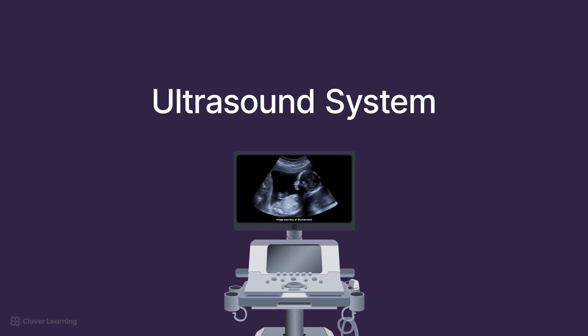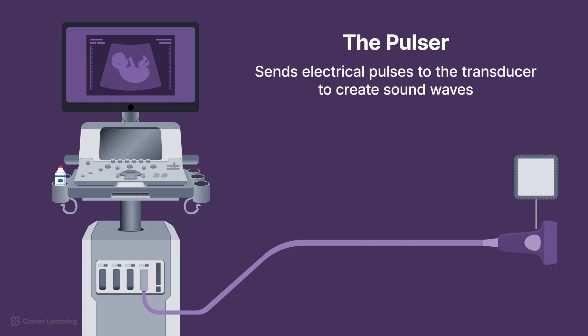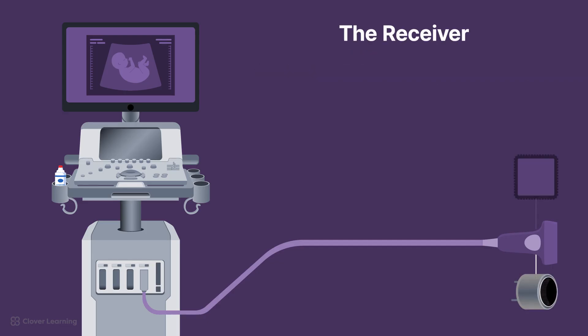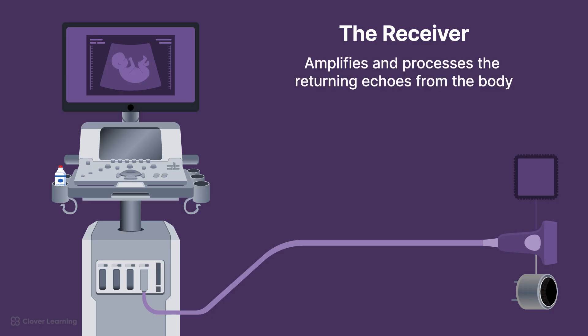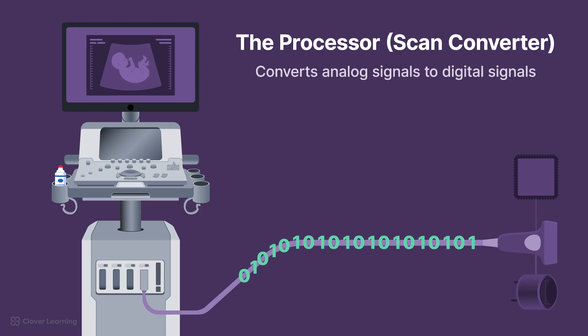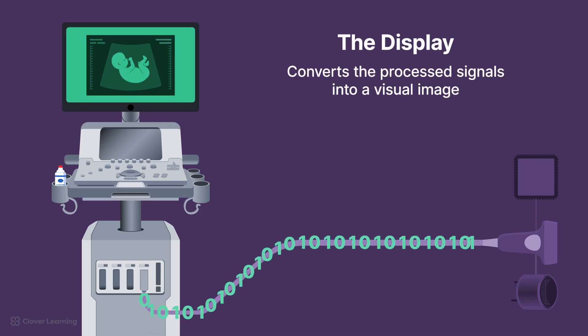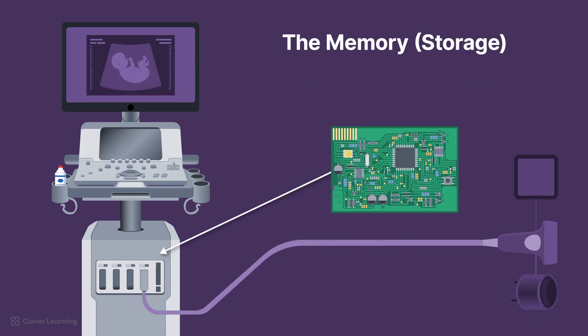The ultrasound system consists of the pulser, which sends electrical pulses to the transducer to create sound waves; the receiver, which amplifies and processes the returning echoes from the body; the processor or scan converter, which converts analog signals to digital signals; the display, which converts the processed signals into a visual image; and the memory or storage, which stores images and patient data.